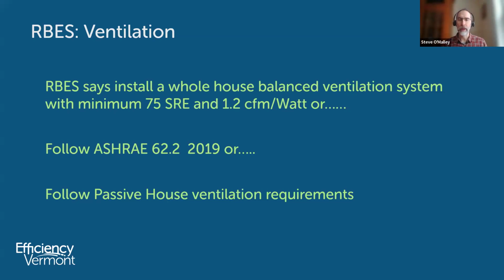When they're running at full capacity, they're not running at their peak efficiency in terms of recovery efficiency. It turns out, if you can slow the unit down a little bit so that you're slowing the airflow through the recovery mechanism, they do a measurably better job of recovering energy. So a rule of thumb is 75%. If your building needed 750 CFM, buy a piece of equipment that is sized for a maximum capacity of 1,000 CFM, and then you operate at 750 CFM. Now you're going to get the higher recovery efficiency out of your core, and better performance.